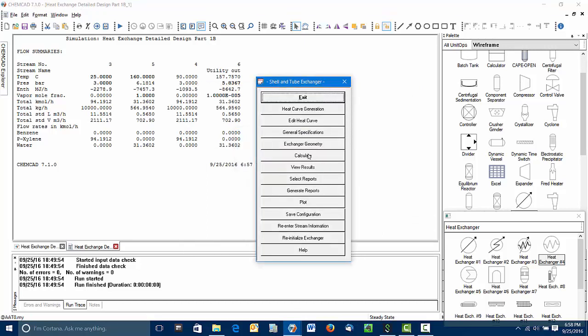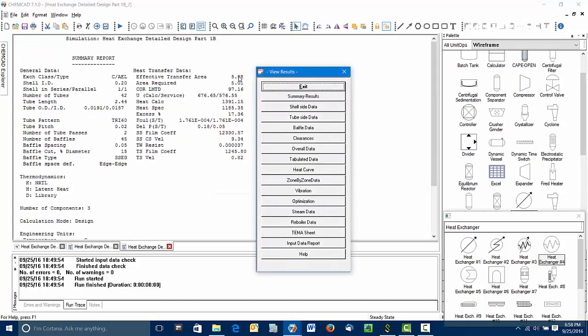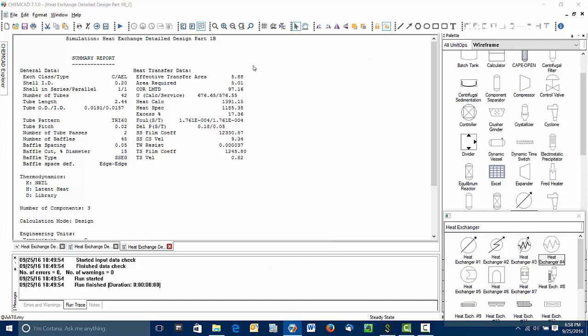No errors. Let's take a look at the results. And it's coming up with about six square meters as the effective heat transfer area for the design it came up with. It needs about five square meters. Just working with standard dimensions it needs six. But this looks like a pretty reasonable design. The area may be a little bit low for a shell and tube exchanger, but that's a different discussion.